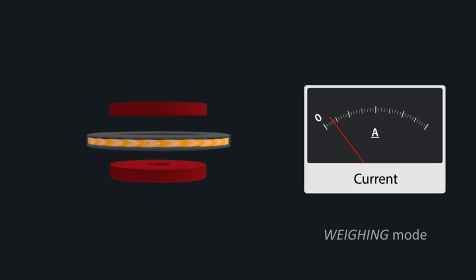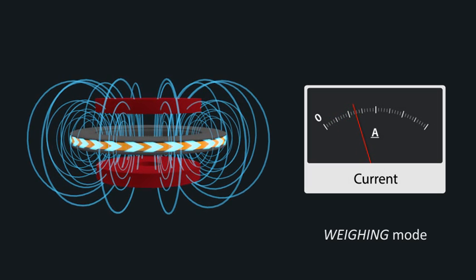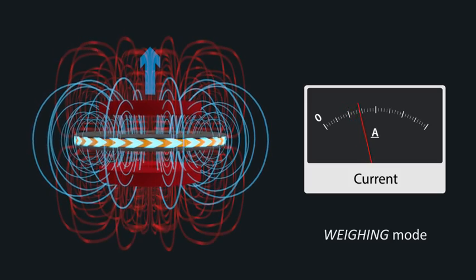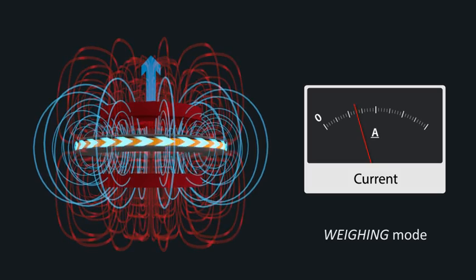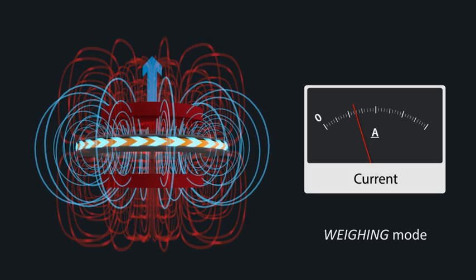In the second mode, called weighing mode, an electrical current is run through the coil to turn it into an electromagnet. As the coil's field interacts with that of the permanent magnets, an upward force is exerted, proportional to the current, which can be measured.